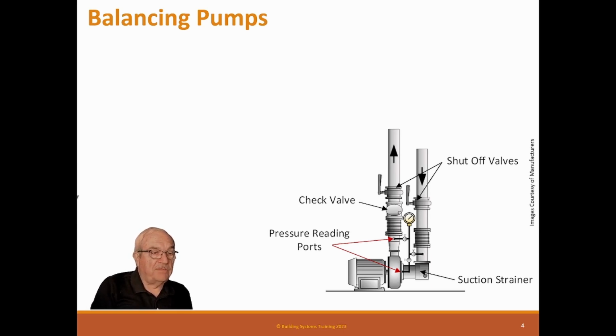So if you have a balance valve on a pump, you actually have two balance valves in series. Makes absolutely no sense. And the other reason not to put a balance valve there is because someone will use it. What I'm saying by that is, all it does is induce a system pressure, which costs you horsepower, which costs you energy forever. Best practice is never, ever to have a balance valve on a pump. I guess unless there was only one thing a pump was feeding and you didn't want to put anything downstream, but whatever the load was, you could put it here. But it's nonsense. It really needs not be there.